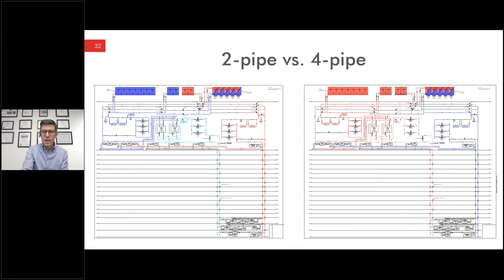And this was one of the more complicated aspects of the Weill Cornell design, mapping out this 4-pipe system arrangement, because it did add some complications, but it ended up being a pretty good solution, and it allowed the simultaneous machines to operate pretty efficiently when we had that simultaneous load. The last thing I'll talk about in terms of the comparison was the difference in the air source heat pump.